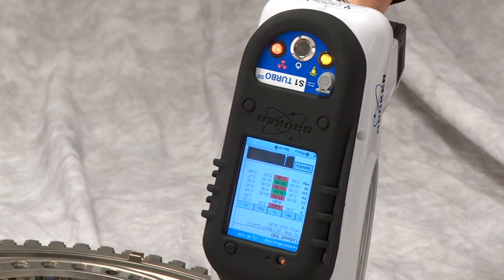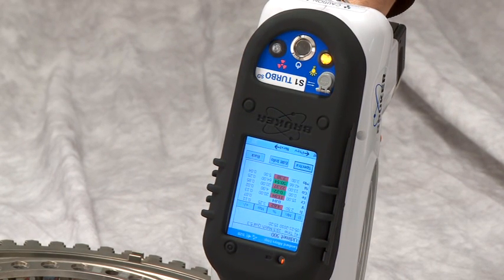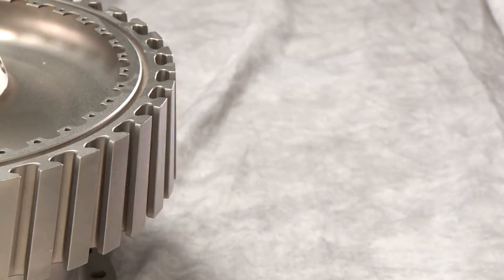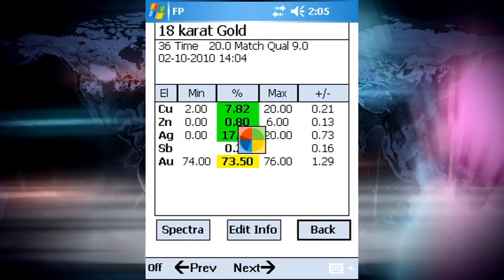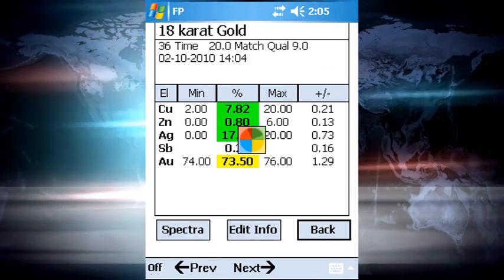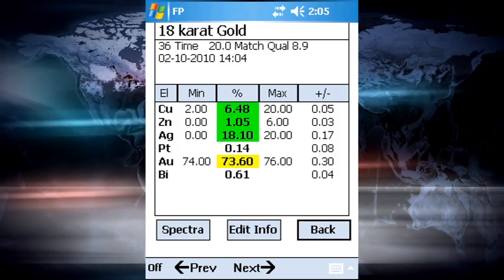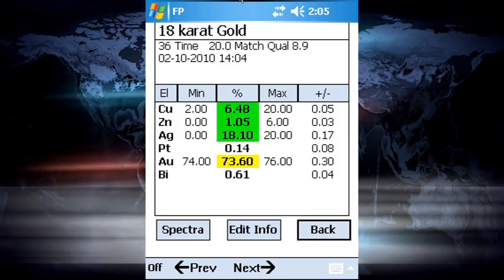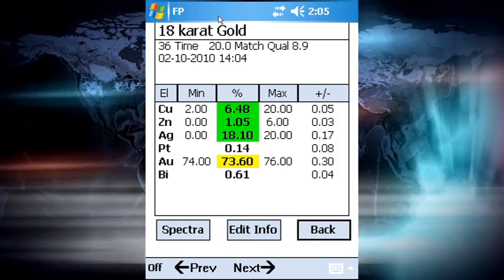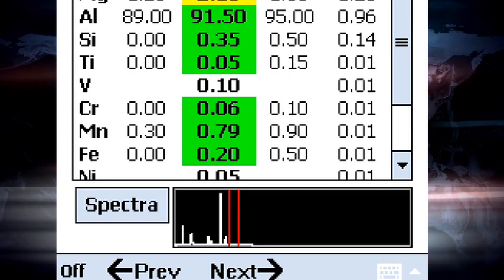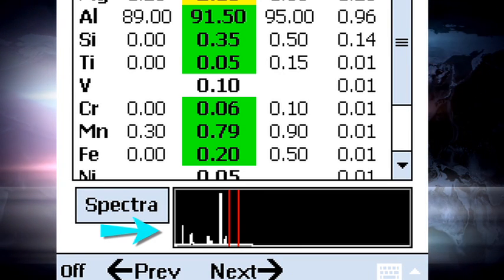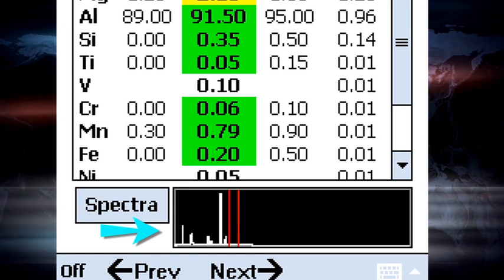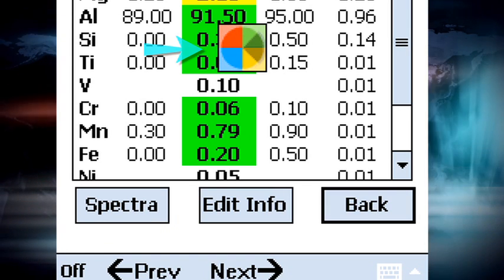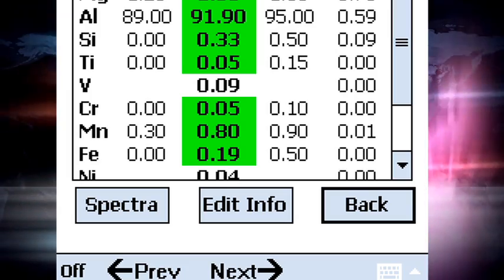At the end of each measurement, there is a slight delay after releasing the instrument trigger. This allows the assay to be calculated and the measurement conditions to be reset for the beginning of the next measurement. In the case of a fundamental parameters analysis, this time may be up to about 10 seconds. It is essential to wait for the completion of the measurement before activating the trigger for the next measurement. The best way to be certain that the measurement is complete is to look at the bottom of the screen. When the small spectra at the bottom disappears and the FP spinner is not present, the analyzer is ready to perform the next assay.